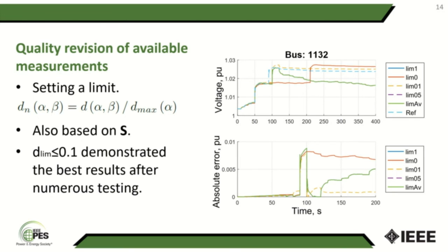To address this last issue, we used a quality limit, also based on dissimilarity as in this expression. All candidate buses to calculate the pseudo measurements are checked, and only those with quality value lesser than the imposed limit are considered. If there are not sufficient candidates, then the bus is taken out of the control pool. We tested several values for the limit and noticed the best one is 0.1, as it is restrictive and does not allow for the remote buses to be taken into account. Nevertheless, the controller is not expected to reach this condition unless a grid scale event occurs.